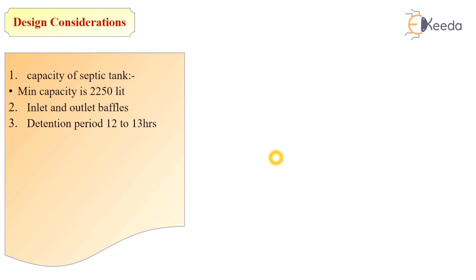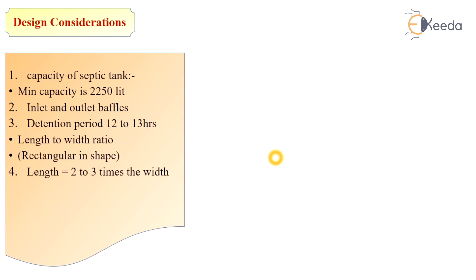Then detention period — generally we consider the detention time for sewage retained in the septic tank as 24 hours, but normally we take it as 12 to 13 hours. The next important parameter is length to width ratio. Septic tanks are rectangular in shape and its length is equal to 2 to 3 times its width. Height and width should not be less than 90 cm, and depth should be 1.2 to 1.8 meters.